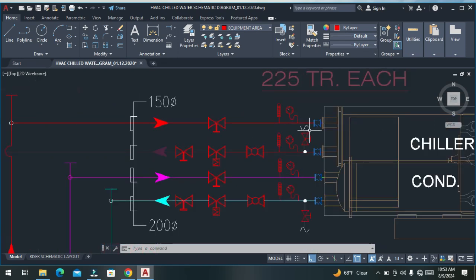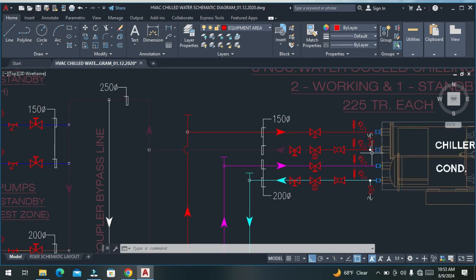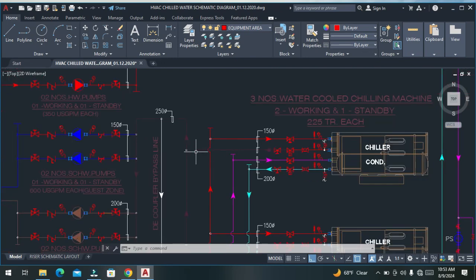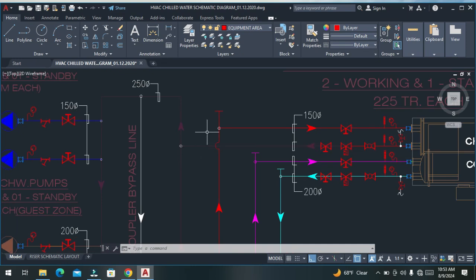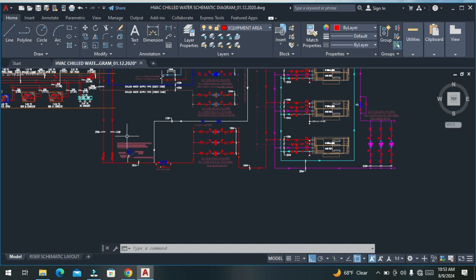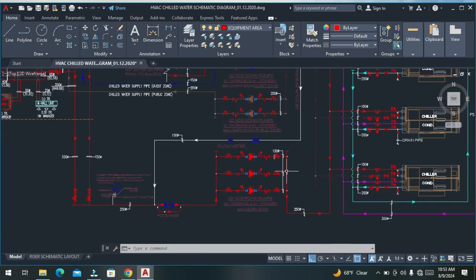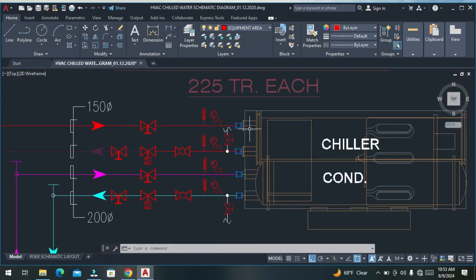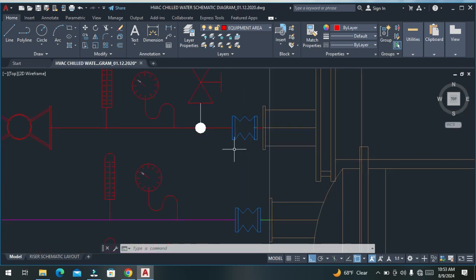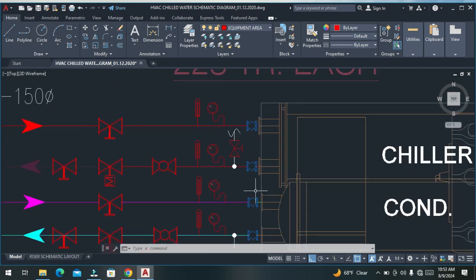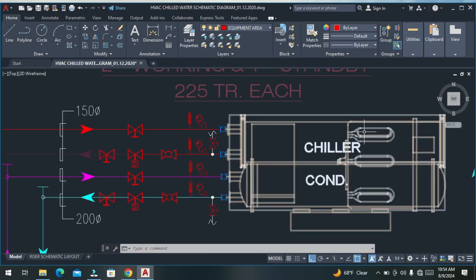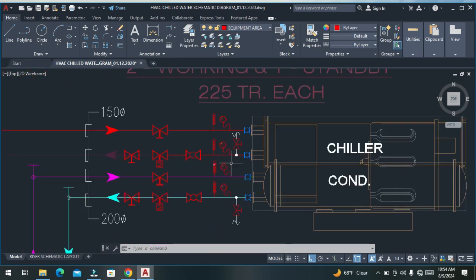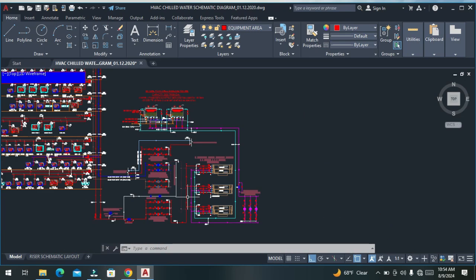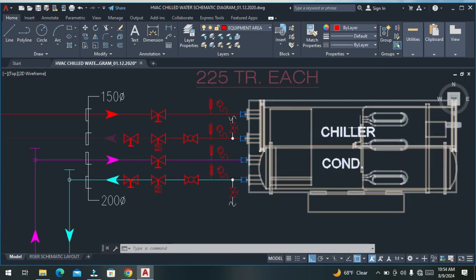If you talk about the pumps, the secondary pump takes chilled water from the evaporator output and supplies it to the units, air conditioning units like HVAC, TFA and AHU. The primary pump takes the chilled water return from the units and supplies it to the evaporator inputs of the chiller. Here the water is at 7 degrees Celsius output, then over here 11 degrees. That means this 11 degree water again enters the evaporator and is cooled by the refrigeration, and then again it outputs at like 6 degrees Celsius, and goes again to the units for chilling purposes in the respective area. So in this way it will work.